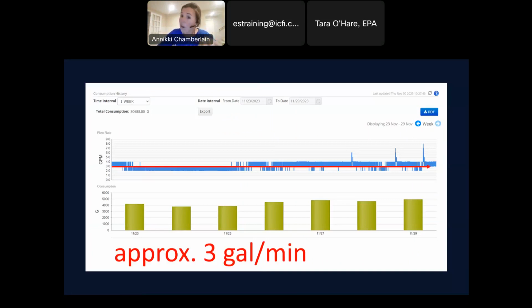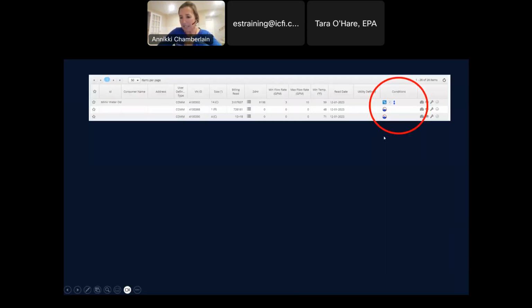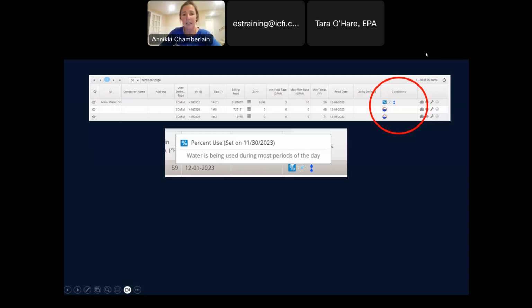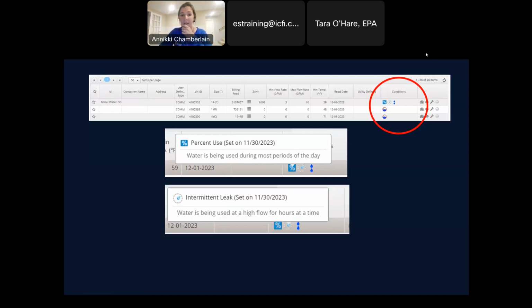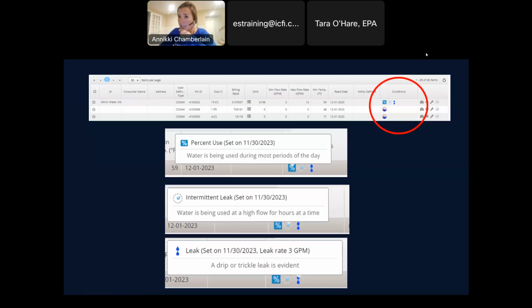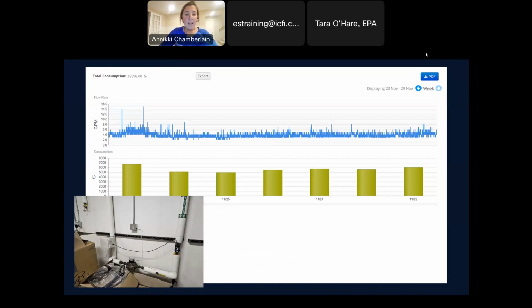But what's great is we were already metering the cooling tower at this location. So that's going to give me an alarm. These are the types of alarms for this service, but again, they come different. It's going to basically say water's being used most periods of the day. That's useful for that water cooled, right? Because it should be turning on, off, on, off. High flow for hours at a time, or basically it's looking like a leak. So these are different algorithms you can set in this WaterScope dashboard, set these parameters, and it'll give you these alerts. But again, we were already monitoring the cooling tower, which is nice.